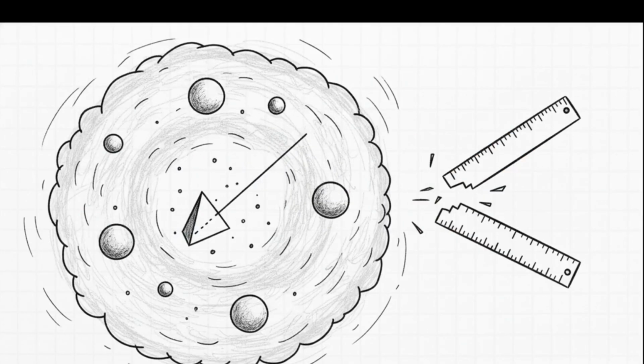Think about it like this. If the assumptions in the model don't perfectly match your real-world sample, a traditional calibration is absolutely not going to save you. There are simply way too many complex variables at play here. I mean, for the model to work flawlessly, it has to assume spherical particles, dilute suspensions, and known refractive indices. And that's before we even talk about the instrument factors. You've got physical alignment, the exact laser wavelength, detector sensitivity, the scattering angle, and the optical properties of the sample itself. You literally cannot use a simple standard calibration curve to magically calibrate away a slightly different scattering angle or some weirdly shaped particle. It's just too complex.